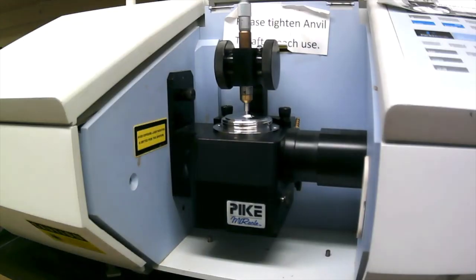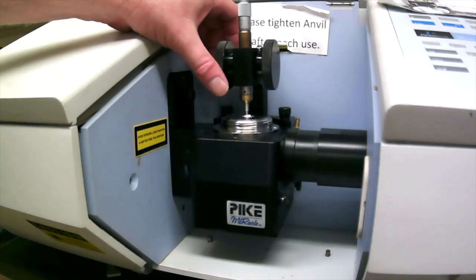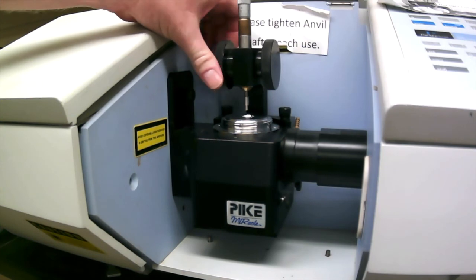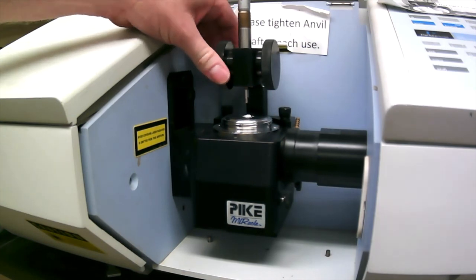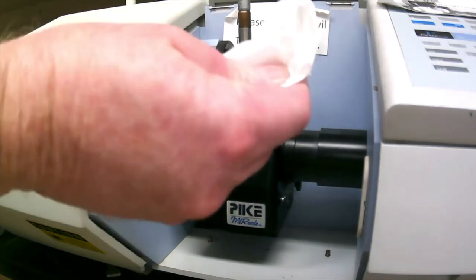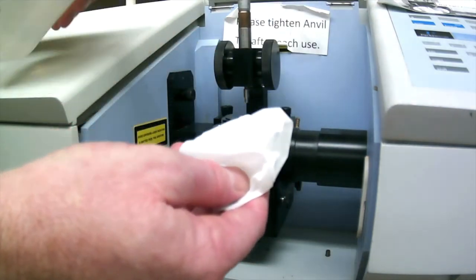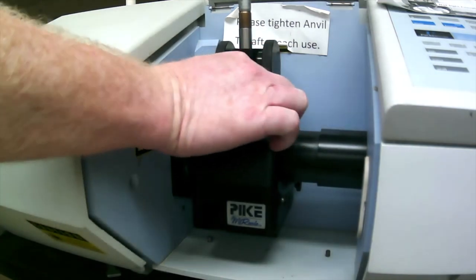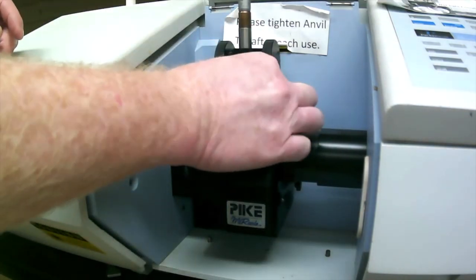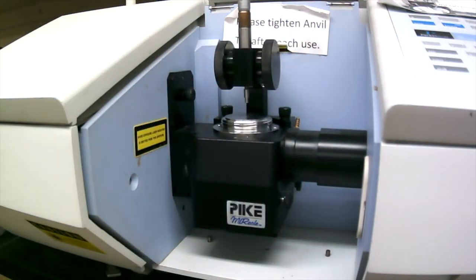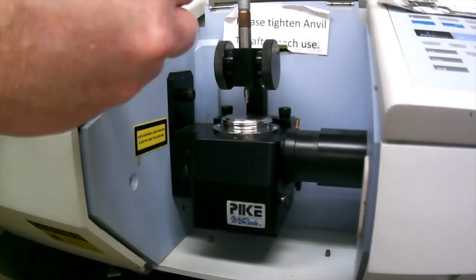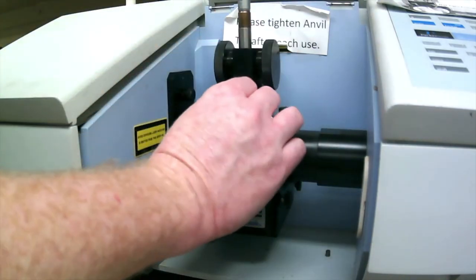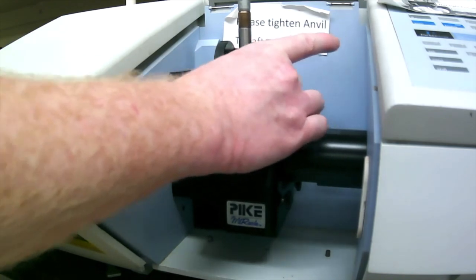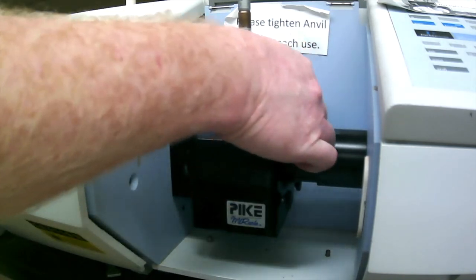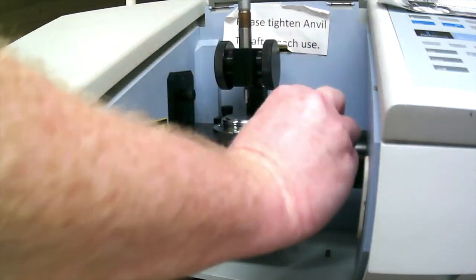For our sample on the ATR adapter, how are we gonna clean this off? What you're gonna do is screw the anvil up, and then you're gonna take a chem wipe and get it a little wet with ethanol. Use that to help you grab onto the vanillin. If you were using something that's more dangerous than vanillin, you can use gloves for this. Or if it is uncomfortable, you can use gloves, but this vanillin's not too dangerous. Put it in your coffee. And then you can wipe it up good. I got another wet one, and I'm gonna wipe the tip of the anvil too. I had a little bit of overspray here. I'll get that too.